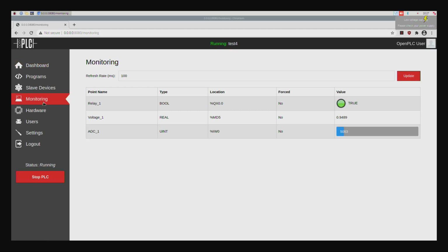What you see on the extreme right top column is the voltage value, and there you see the voltage which is 0.9 volts, and this corresponds to 0 bar. Now we have set it to 0.2 bar, a very small rise in pressure, and that corresponds to a voltage of 1.2 volts. Let us see what actually happens at 1.2 volts.